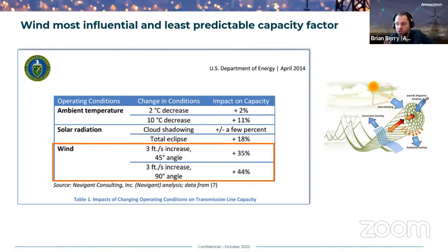So if I look at all the inputs that can go into a line: ambient temperature — a 2-degree decrease relates to a 2% increase in capacity, and 10 degrees Celsius, which is a lot, gives me an 11% capacity increase. Solar radiation — middle of the night versus middle of the day gives 18%. Not bad. But cloud shadowing can change that.